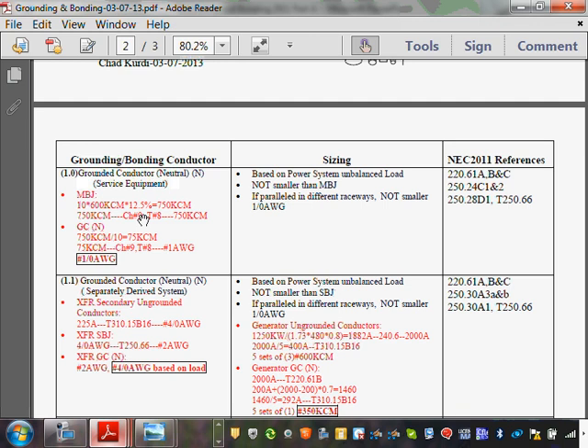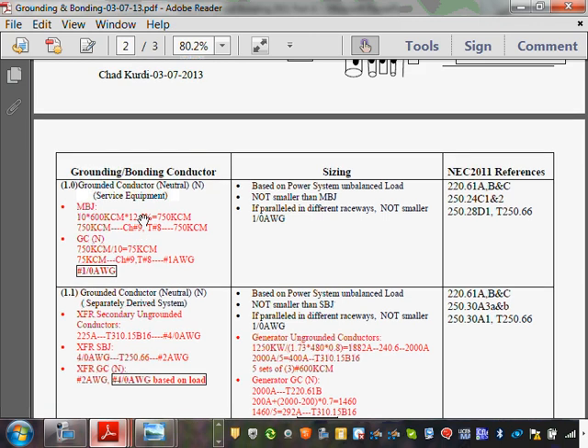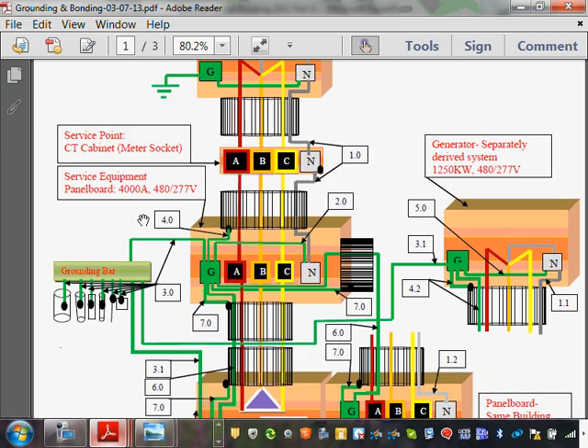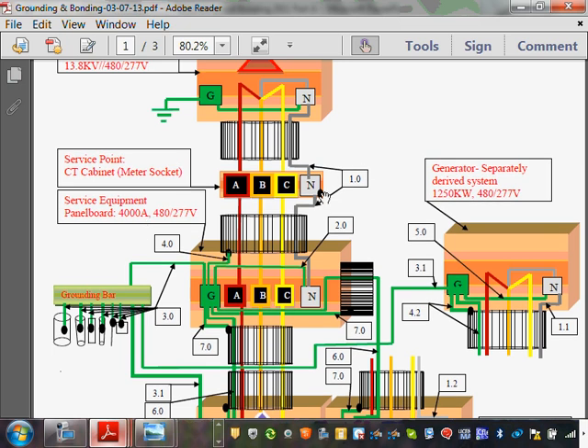Any comments about that? So now we brought the neutral and we sized it. Then if you go back up, now we brought my neutral. The first thing that happened right here on the meter socket, now the switch gear, guys, is right here. Inside the switch gear, you will have a 4,000 amp circuit breaker sitting right here. Anything on this side is called the line side of the service disconnect means. You guys remember that? That from here up, that's a line side of a service disconnect means. The code allows you to use the neutral to ground anything on the line side of the service disconnect means.